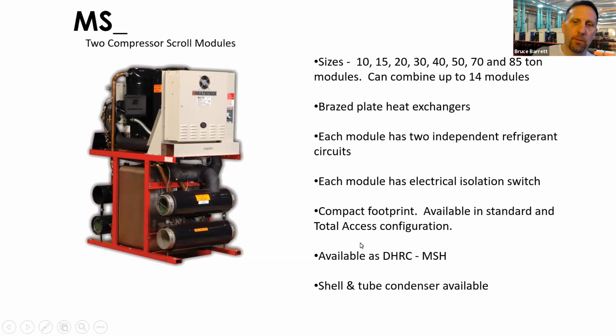Again, very compact footprint. Same models we use a lot for our heat recovery chillers. We do offer a shell and tube condenser bundle. It does change the footprint dramatically. That's one of the bonuses of braze plate is you can get very, very compact. Shell and tube is going to get larger.